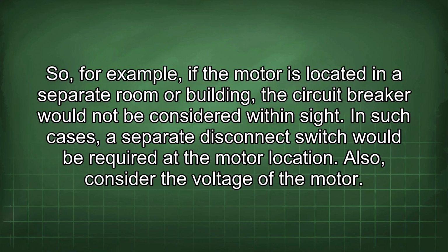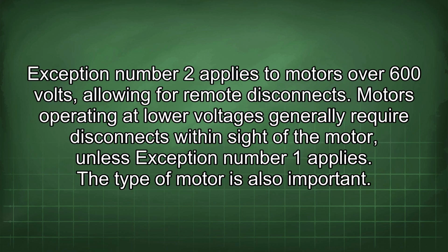So, for example, if the motor is located in a separate room or building, the circuit breaker would not be considered within sight. In such cases, a separate disconnect switch would be required at the motor location. Also, consider the voltage of the motor. Exception number 2 applies to motors over 600 volts, allowing for remote disconnects. Motors operating at lower voltages generally require disconnects within sight of the motor, unless exception number 1 applies.